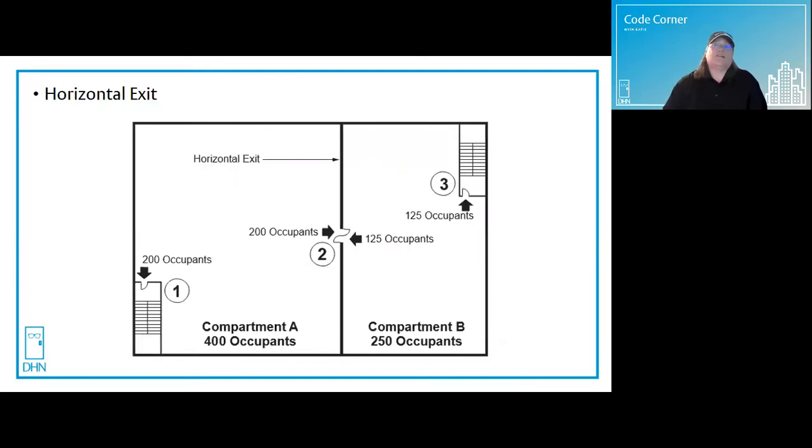A horizontal exit is an exit component consisting of fire resistance rated walls, floors and ceilings, and fire rated door openings. It is intended to compartmentalize portions of a large building into smaller compartments of no more than 22,500 square feet, thereby creating refuge areas that afford safety from the fire and smoke from the area of fire origin. We have a horizontal exit on the screen. It's that double egress door in that fire barrier. And it separates compartment A from compartment B.